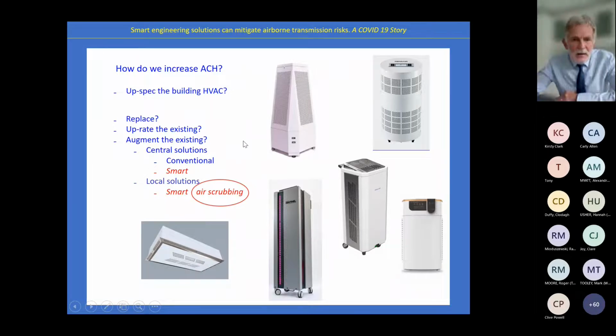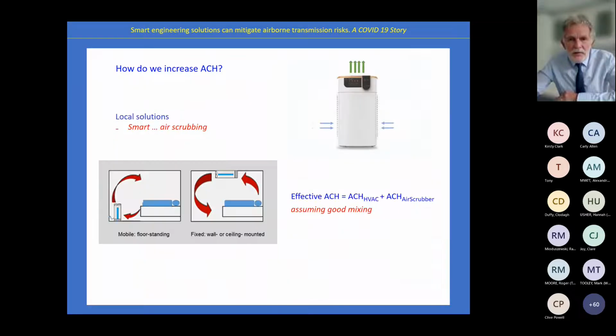This is smart air scrubbing. Here are six examples of local pieces of kit that can be wheeled into a room or bolted to the ceiling, recirculating air locally and adding to the number of effective air changes per hour.